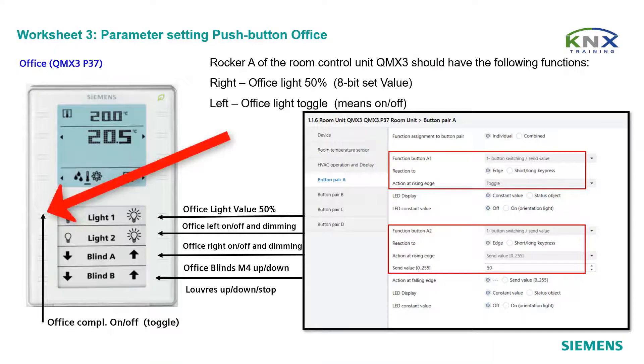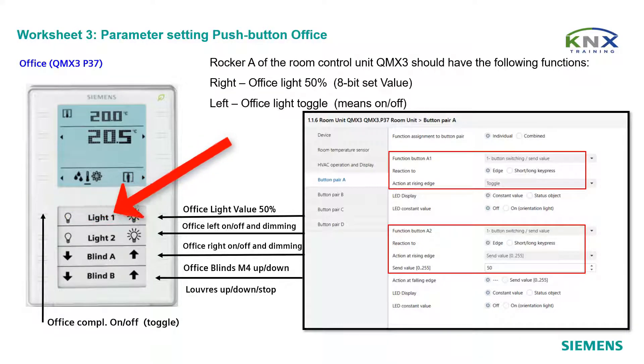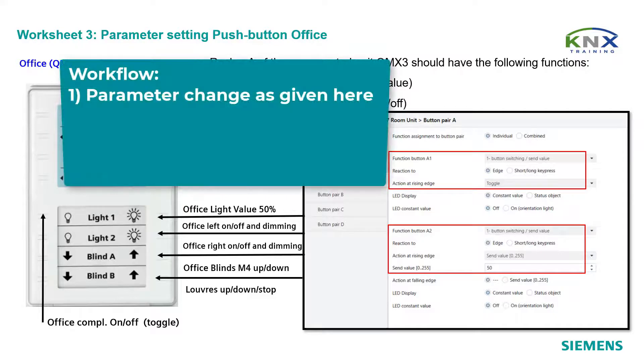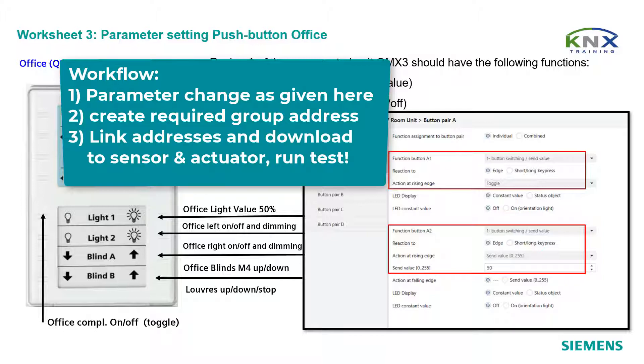That leads to the following configuration of rocker A: left button equals toggle on/off, right button equals value control sending 50%. Do the three steps: 1. Parameter change as given. 2. Create the required group address. 3. Link addresses and download to sensor and actuator. Then test the new function.